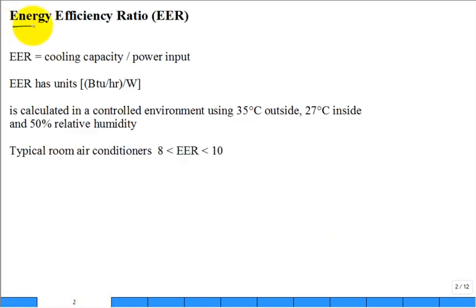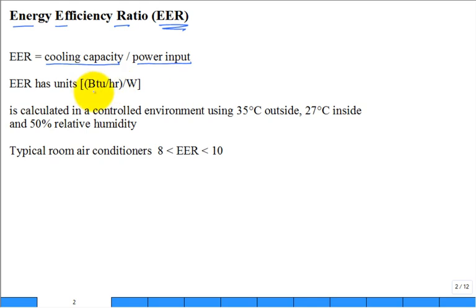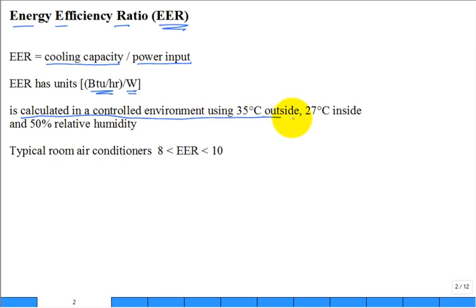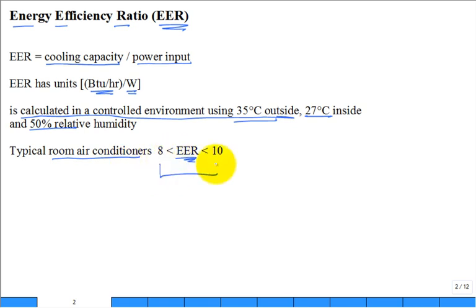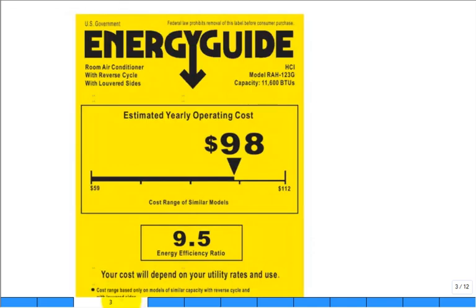First is the Energy Efficiency Ratio — EER. It's defined as the cooling rate divided by the power input. The units are BTU per hour divided by watts. The air conditioning system is tested under controlled conditions: 35°C outside, 27°C inside with 50% relative humidity. Typical room air conditioners have an EER rating between 8 and 10, though some are now above 10.